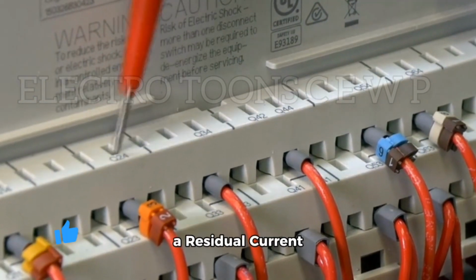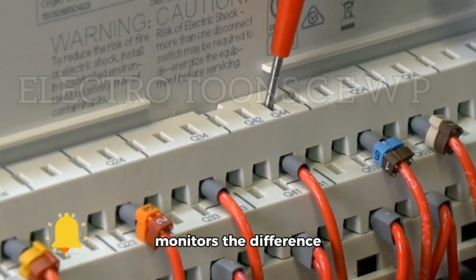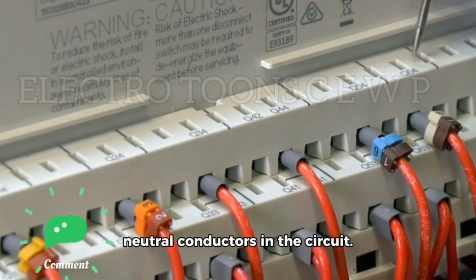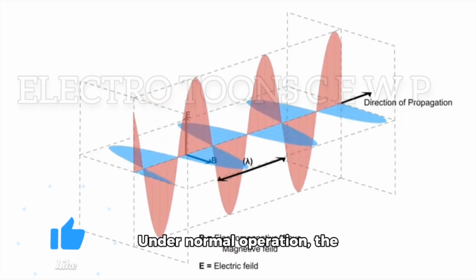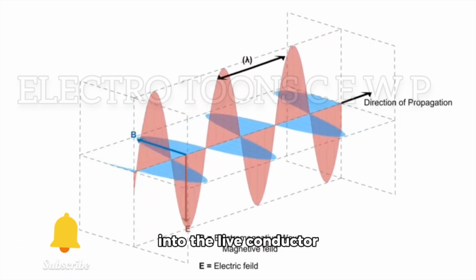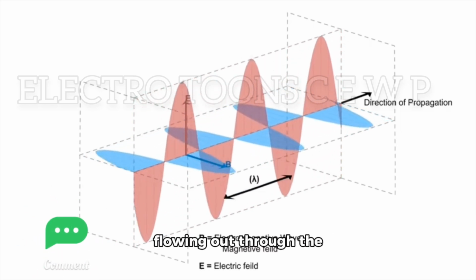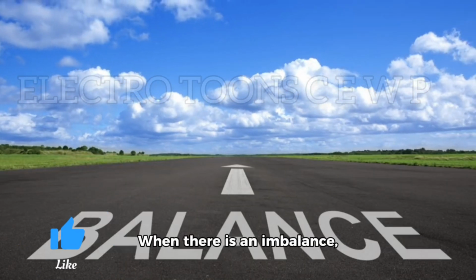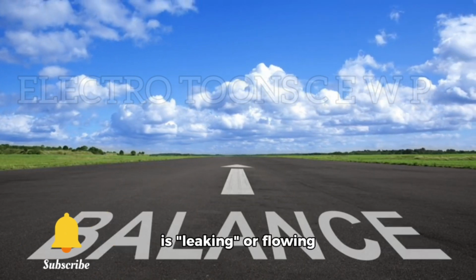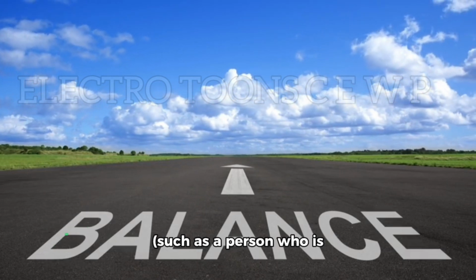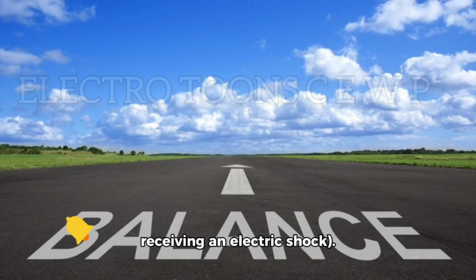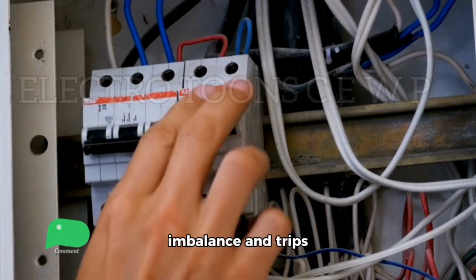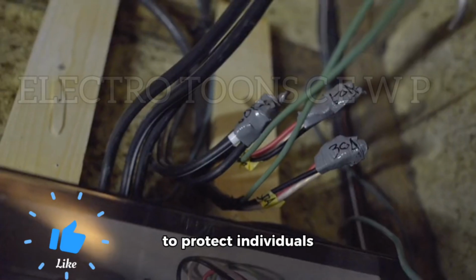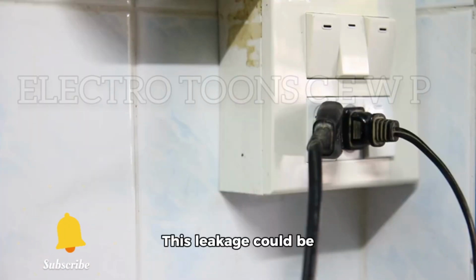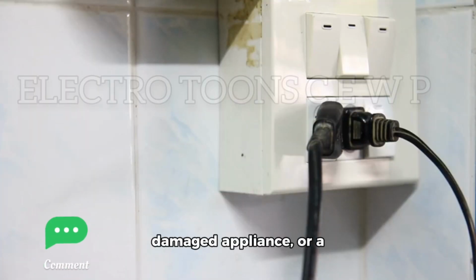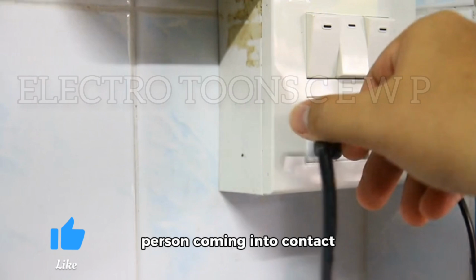Like a residual current device (RCD), the RCBO monitors the difference between the live and neutral conductors in the circuit. Under normal operation, the amount of current flowing into the live conductor should equal the current flowing out through the neutral conductor. When there is an imbalance, it means some of the current is leaking or flowing through an unintended path, such as a person who is receiving an electric shock. The RCBO detects this imbalance and disconnects the circuit to protect individuals from electric shock. This leakage could be caused by faulty wiring, a damaged appliance, or a person coming into contact with a live conductor.